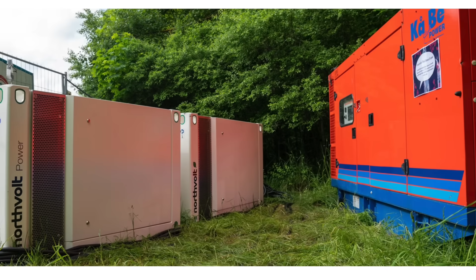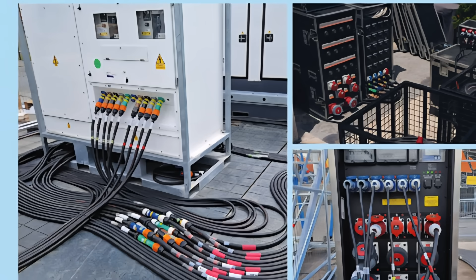But this proliferation of complex temporary electrics has brought new dangers, prompting the authors of the wiring regs to step in with changed advice on best practice. In a newly updated version of its Guide to Temporary Electrical Systems, the IET says electricians need to urgently focus on the earthing of such hybrid arrangements. That's because they're susceptible to circulating currents. These are unintended flows between two or more power sources via their interconnected neutral or earthing conductors. It's not part of the normal load current. They occur if each source shares a common neutral or earth but has a slightly different voltage reference. As a result, current flows through the earth or neutral conductors between sources even when no load is connected.